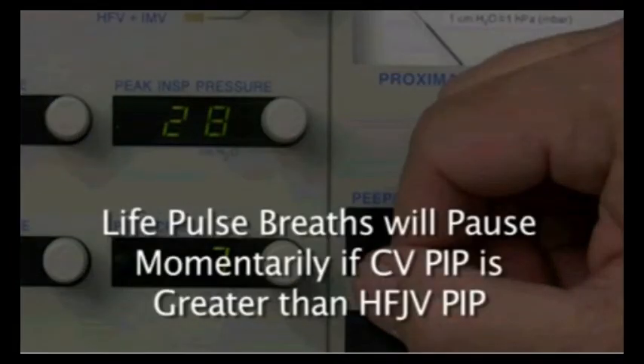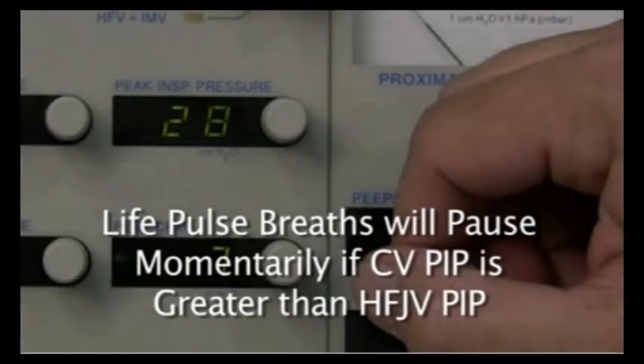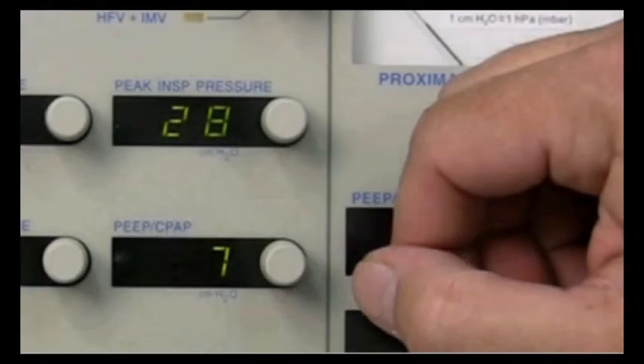Anytime the LifePulse senses a pressure higher than it is allowed to accept, which is determined by the set PIP value, the jet will try to protect the patient by not contributing to what it perceives as a high-pressure condition. When the conventional breath goes away, the LifePulse will begin operating again. So you will hear these intermittent pauses in ventilation if the conventional PIP is higher than the LifePulse PIP.